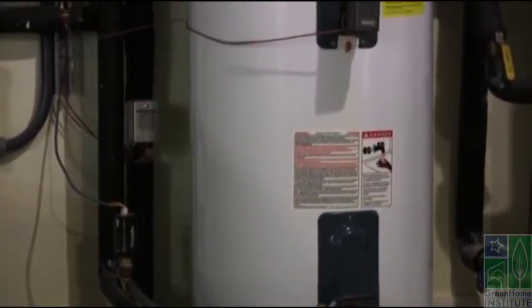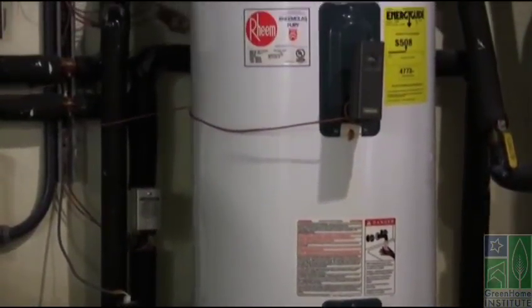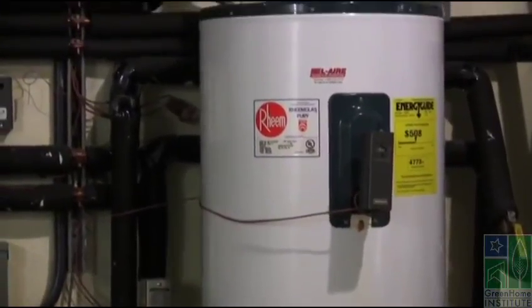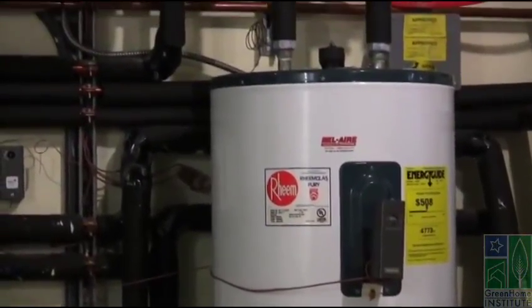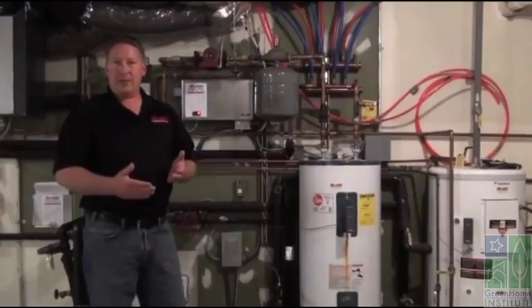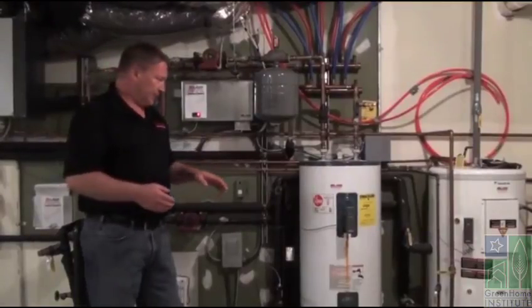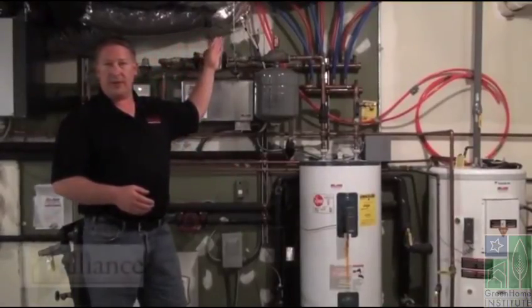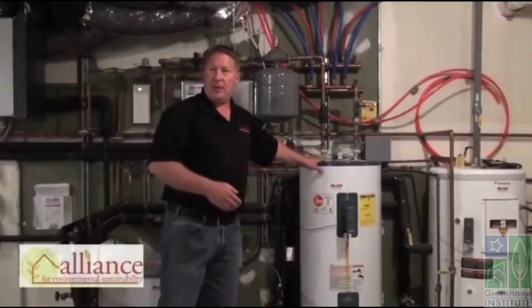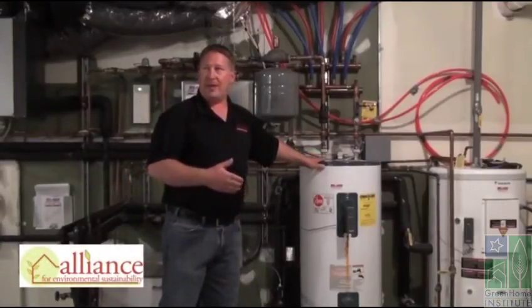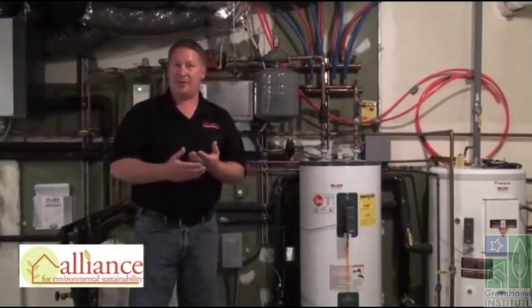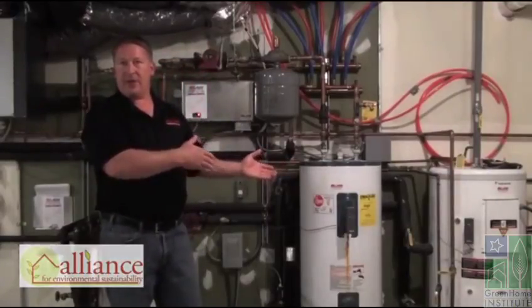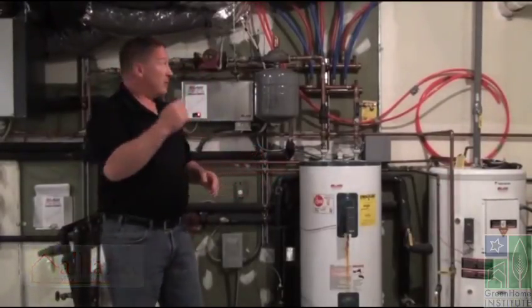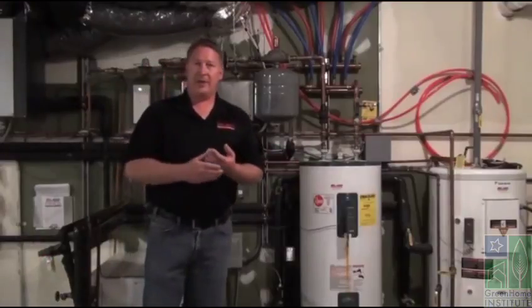This buffer tank really is a thermostat that controls the whole system. So there's a thermostat mounted on the buffer tank, and it's going to maintain a preset temperature about 110 degrees in that tank. So regardless whether the house is calling for heating or not, this buffer tank is always going to have about 40 gallons of water in it that's at that temperature, so that when you make that demand for heating, you already have 40 gallons of water there to circulate through the floor and heat the house.